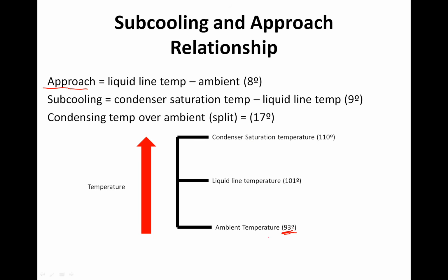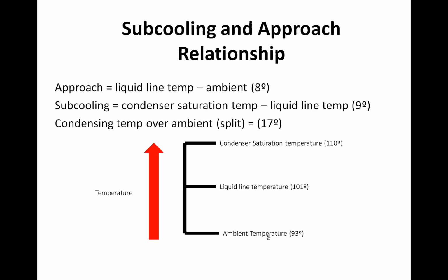That's considered split. On old systems, the old low efficiency, we used to say the condensing temp over ambient was 30. Everybody used to say, oh yeah, it's got to condense 30 degrees hotter. Well, as these systems have gotten higher and higher efficiency, you get up to an 18 SEER condenser, that's no longer plus 30, that might be plus 15, because that higher efficiency condenser is larger, so to reject the same quantity of heat, it needs to be at a lower temperature than that older, smaller condenser that was 30 degrees hotter. And those are just some relationships you need to have in the back of your mind.